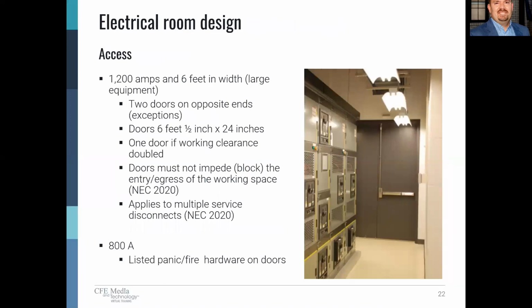So as we look at electrical room design, we want to make sure that we're providing proper access. There's a specific case in the NEC where for gear that's over 1200 amps and 6 feet in length, this is large equipment. We need to provide some unique characteristics of the working clearance. Either 2 doors on opposite ends, so one for entrance and one for exit from the working clearance, and the doors need to be 6 feet, 1/2 inch by 24 inches wide. One door can be provided if we allocate double the working clearance that would ordinarily be provided for this gear. So it's either a door on either end, or it's double the working clearance with a single door.